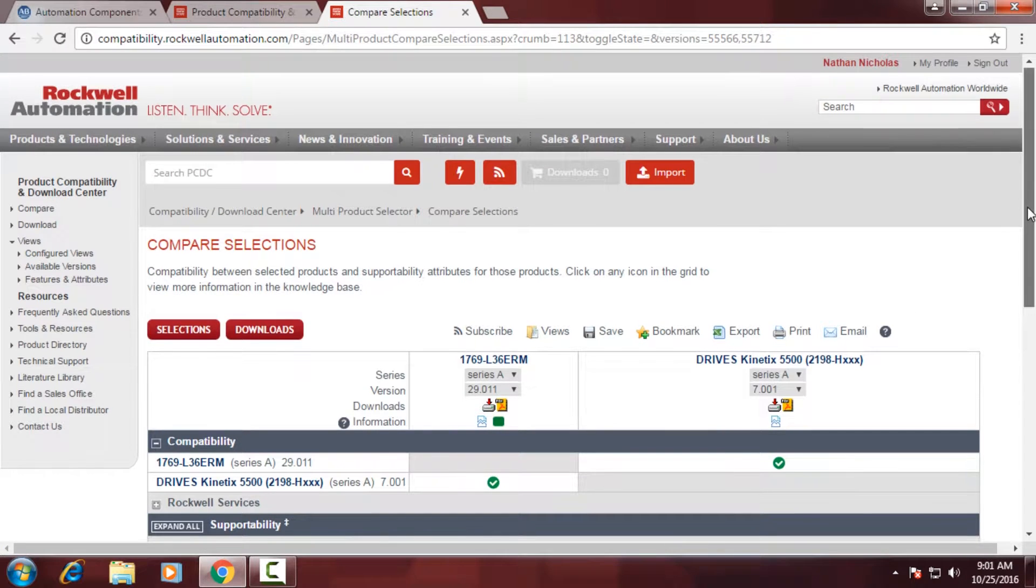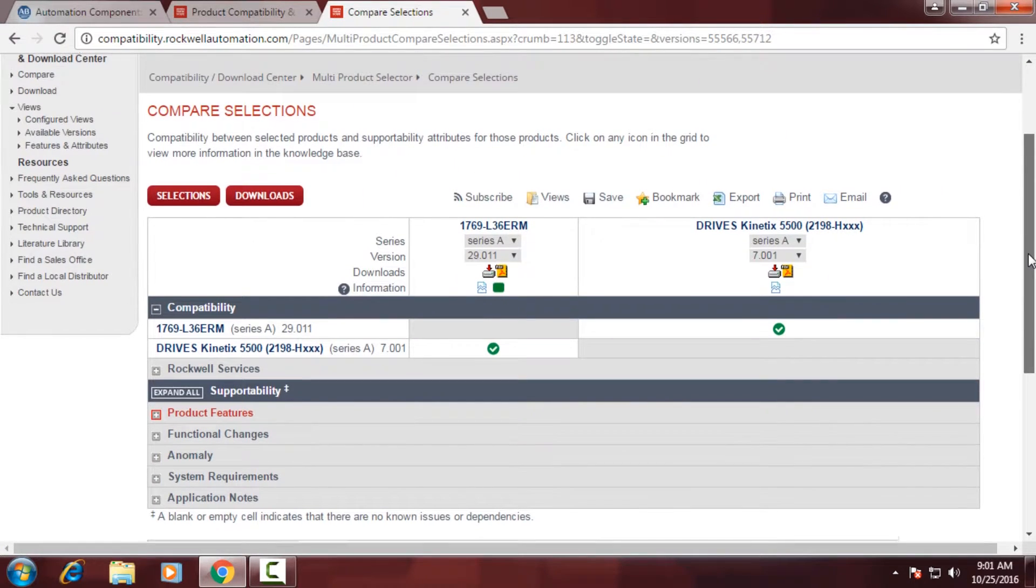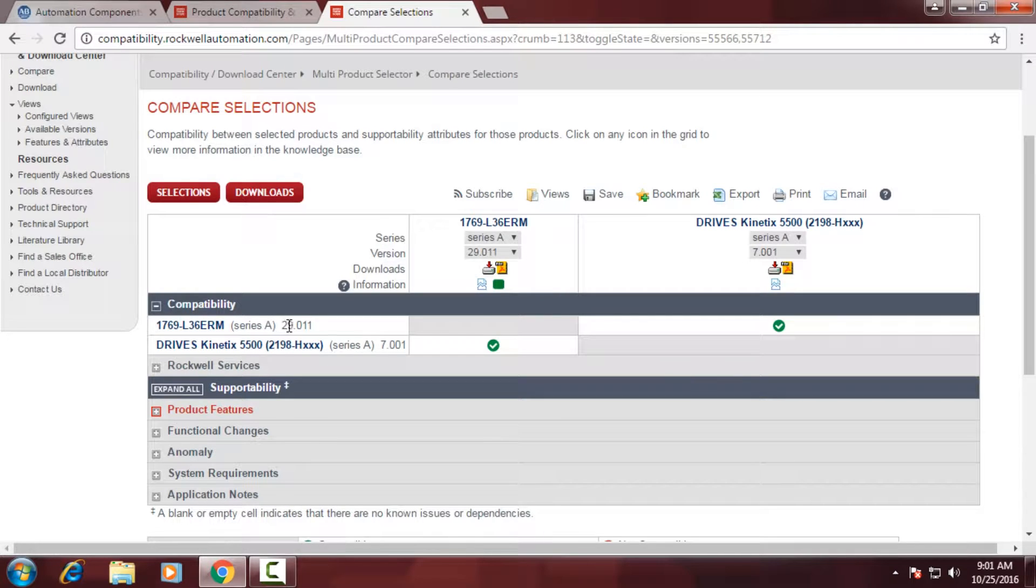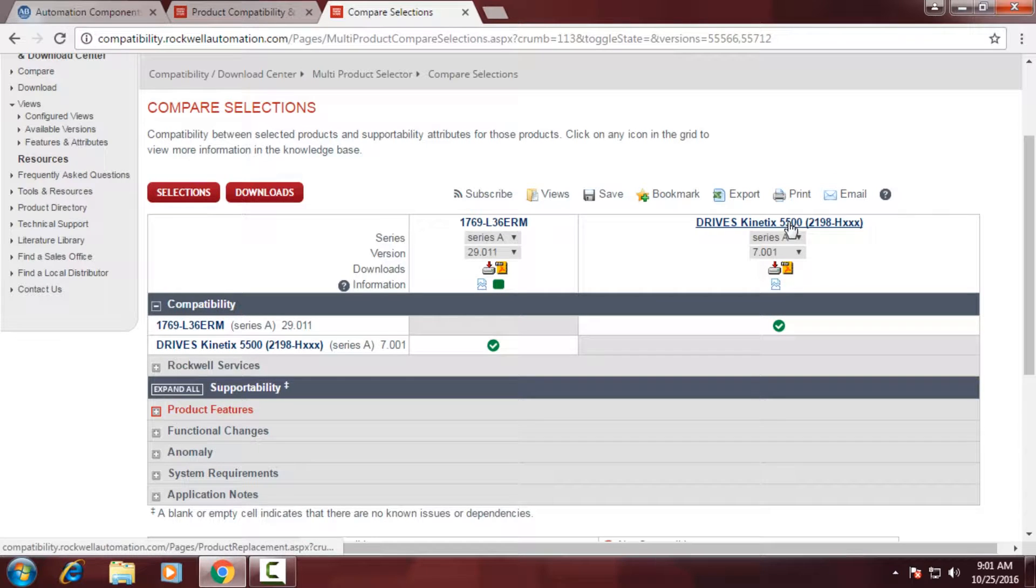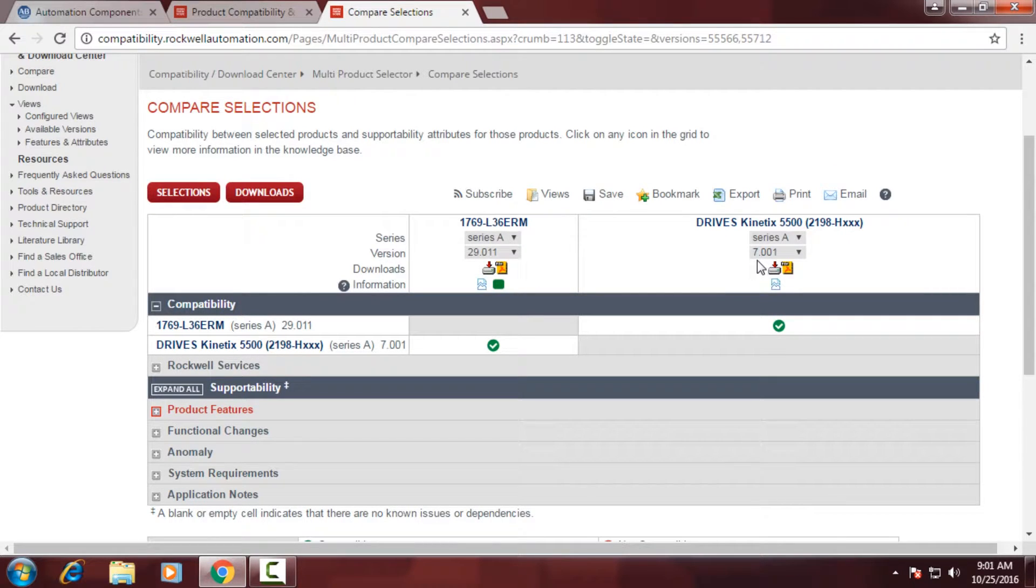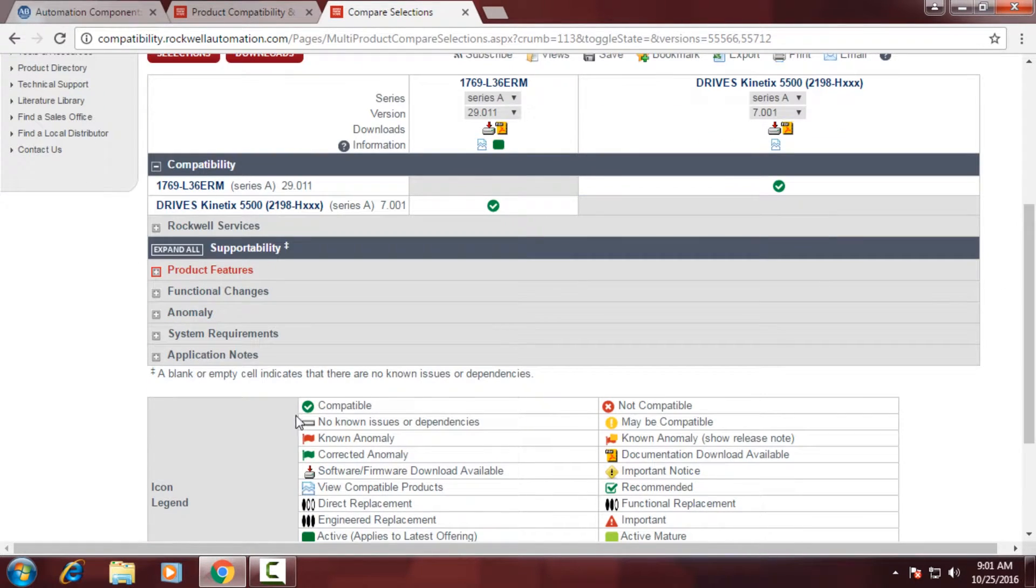We're going to compare these products. You'll notice it gives me a table. And it references the L36ERM with version 29. And it gives me a green checkbox underneath the Kinetix 5500 with revision 7. So I know that these two products are compatible and will work together.